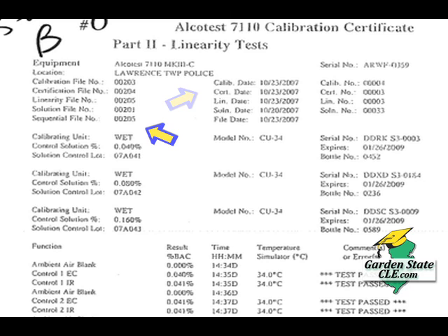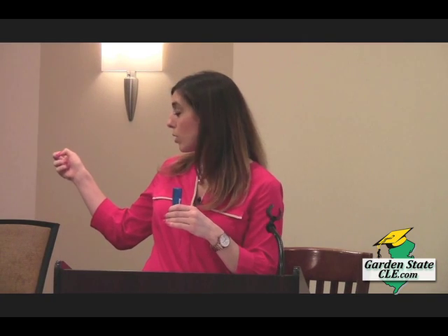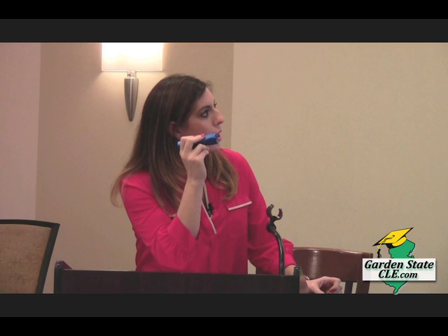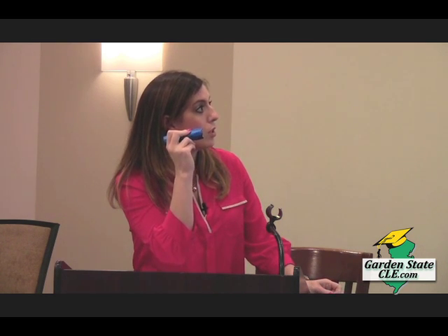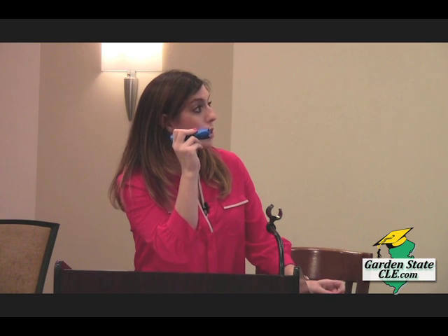Sequential file number, calibration date. Then it's going to go through the 04, 08, 16. Okay, they have to put on, as Sam told you, different calibrating units, different CU34s, right, for each one that they do, because it's got a different solution in it. So there's a serial number for the CU34 for the 04. There's a different solution, it tells you when it expires.